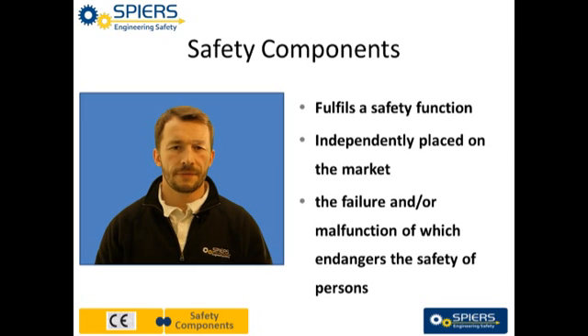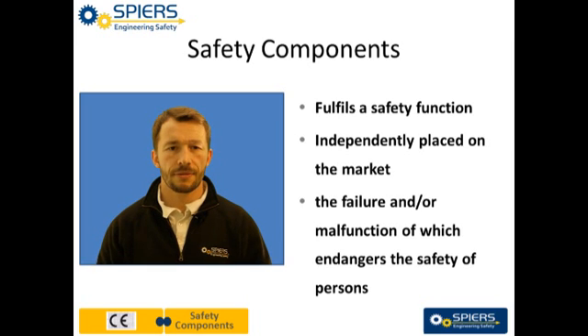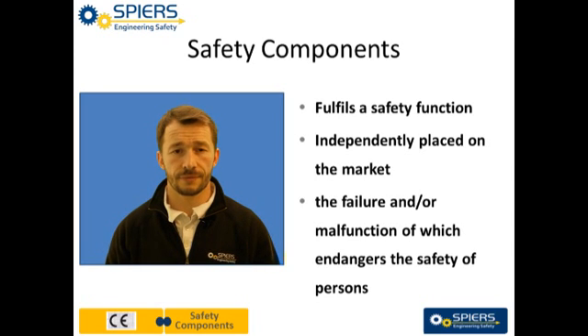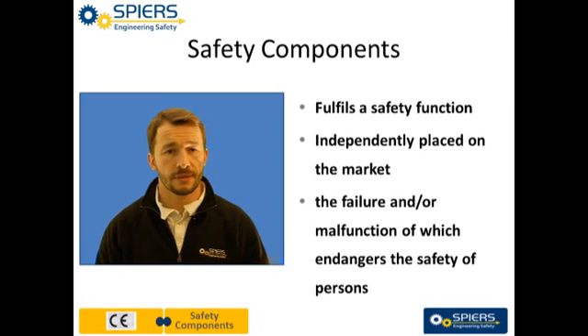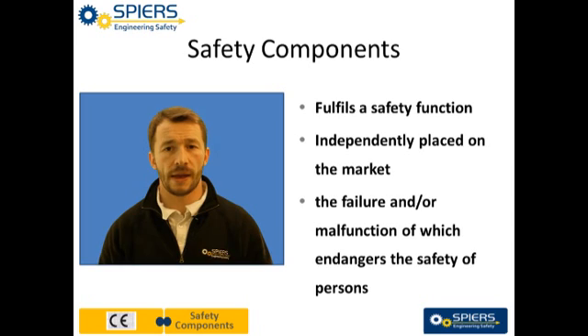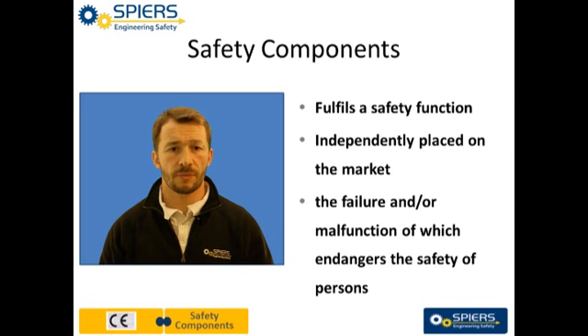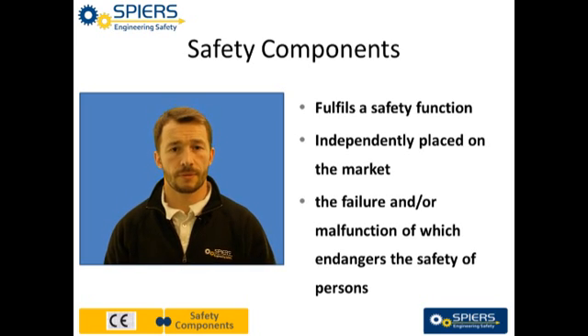When these safety components are integrated as part of a safety related control system, EN 13849 is one of the applicable standards that can be used to assume compliance with the Machinery Directive. Alternatively, IEC 62061 can be used for determining that the remaining residual risk is acceptable for safety related electronic control systems.